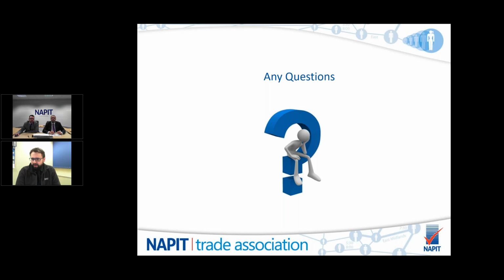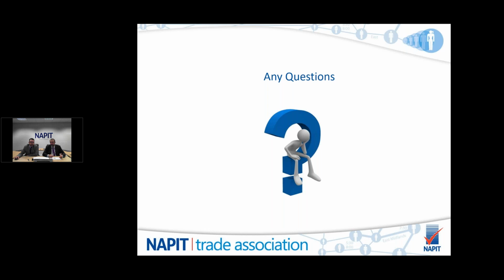Okay, another question we've had concerning the need for the possibility of loss of electrical distributors' earth supply. What of premises where installing an additional earth electrode is difficult, e.g. an upper floor flat, with the proposed draft clause requiring installing of earth rods? This is all part of the problem that we are foreseeing, so this is part of the reason we don't think that particular clause has been well thought out and is a little immature, so we don't think it should be put in, because obviously these things have got to be thought about and they will pose a big problem.